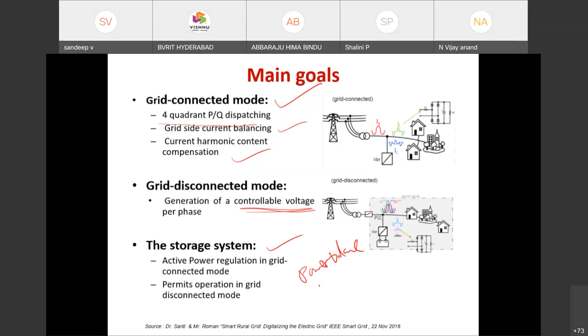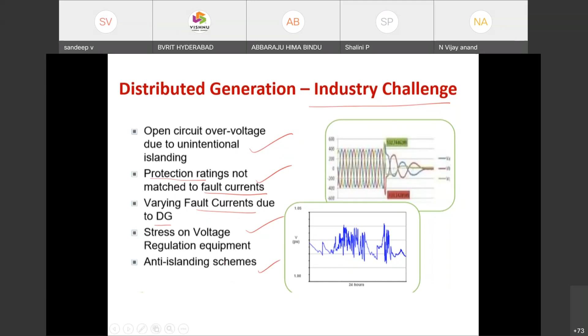And coming to industry challenges, particularly in a distribution grid connected system, one thing we see is over voltage, open circuit over voltage, unintentional islanding. When you do islanding, obviously we'll see some kind of over voltages, and protection ratings are not matched with the fault currents. If they are matched, there is no problem. This protection device will operate, otherwise it will not operate. And then varying fault currents due to DG. And tap and voltage regulation, anti-islanding schemes also will create a lot of power quality issues.